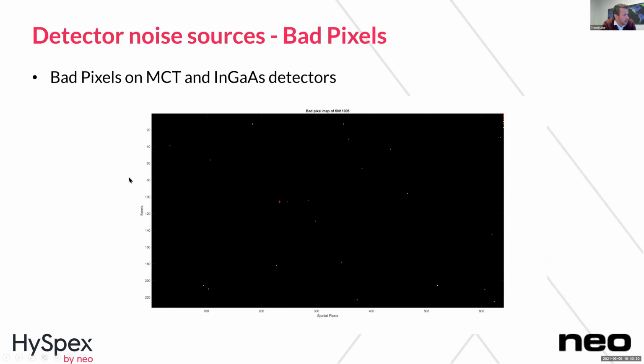And of course, bad pixels for MCT and InGaAs detectors, it's getting a lot better. When I started this 18 years ago, it was about 1 to 1.5% bad pixels in an MCT detector. Today, in MCT detectors, with 20 to 30 micron pixels, you will have about 0.05% bad pixels.